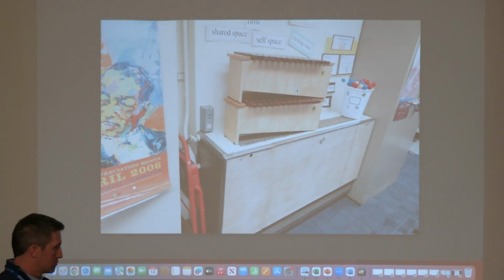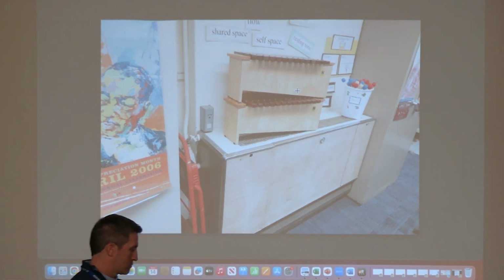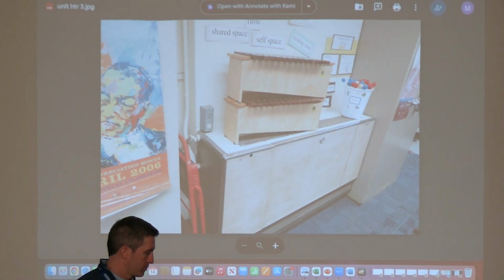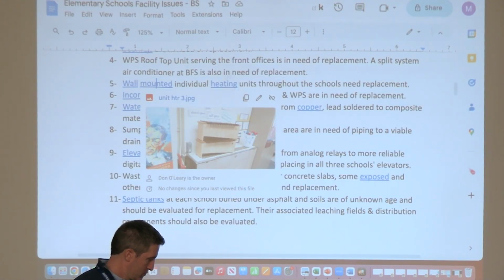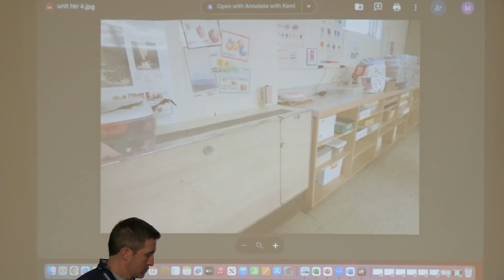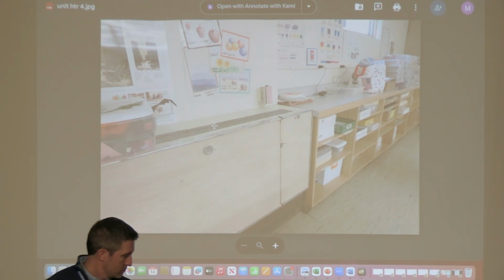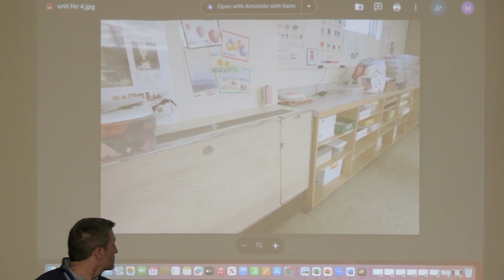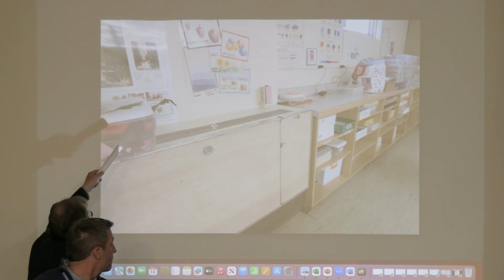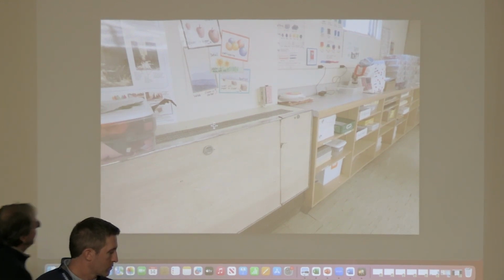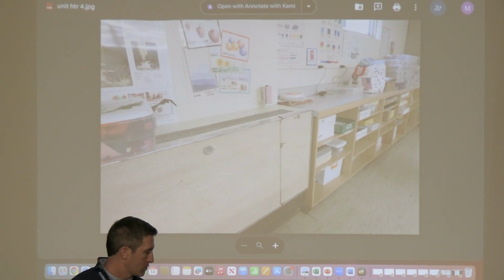That part was disabled. I've been here 15 years and it was already disabled when I got here, the outside air part. So right now it just serves as a heater. A couple of times through the years when we had single digit temperatures for a week at a time, I've had to go into those classrooms. The last time was during Christmas break, and I had to put heaters in that classroom because the coils inside, although they have hot water in them, are exposed to the air inside that box, which I can't get to and we can't insulate. So we didn't want them to freeze.